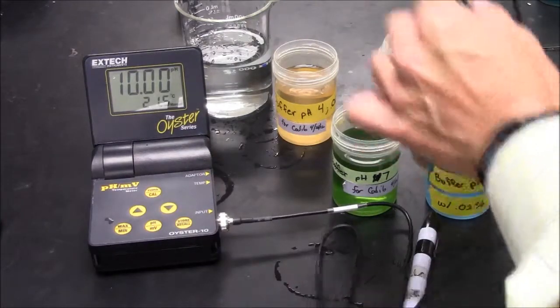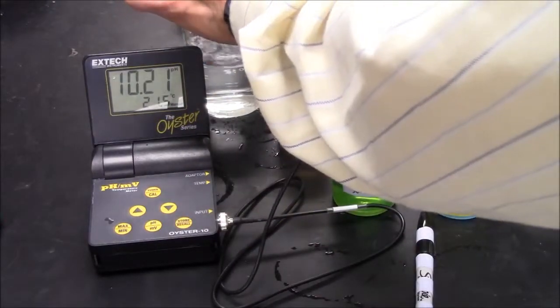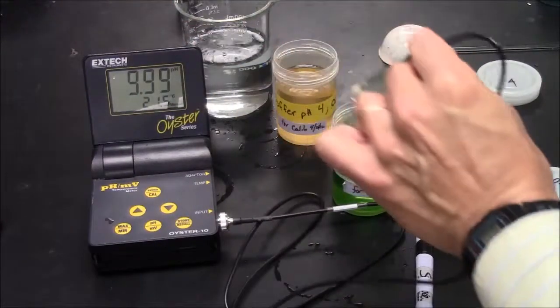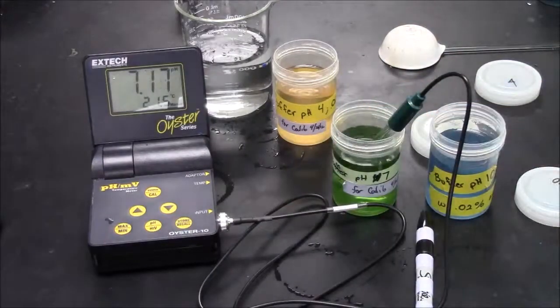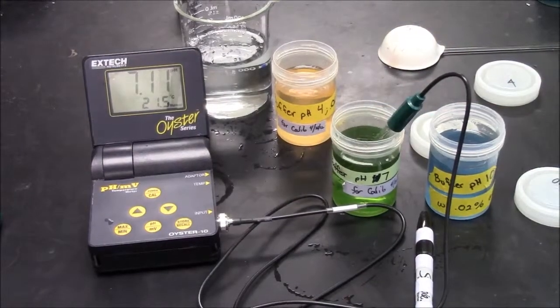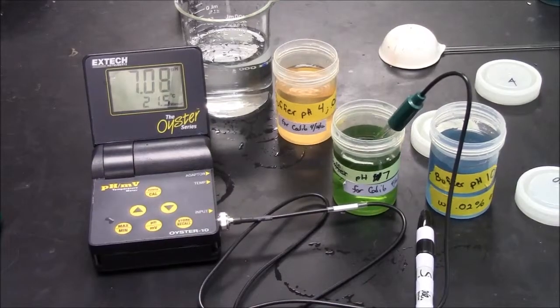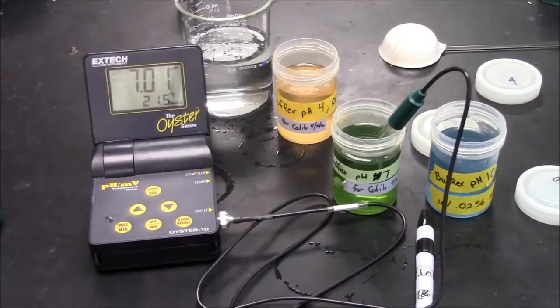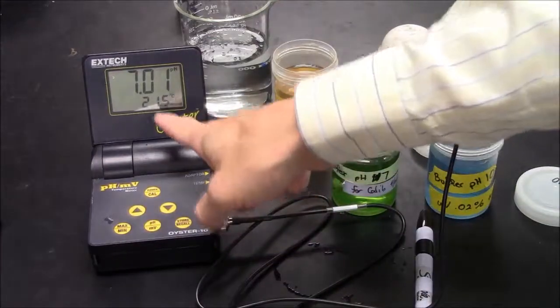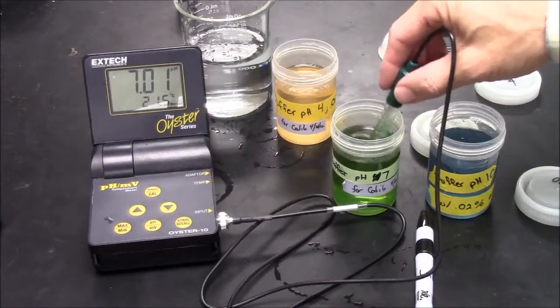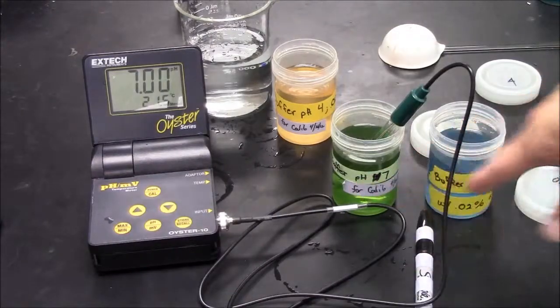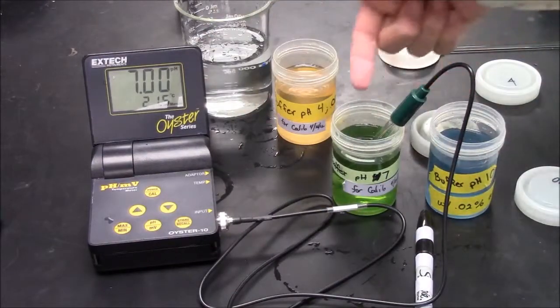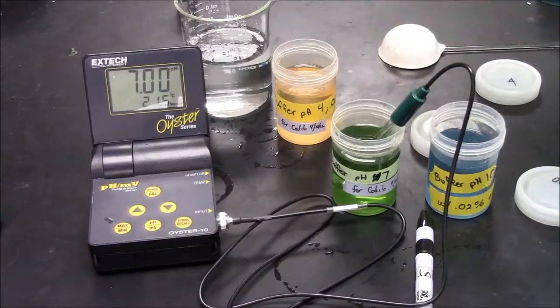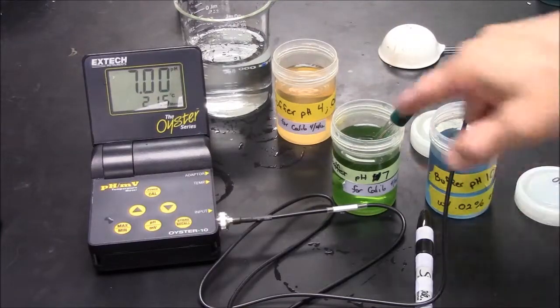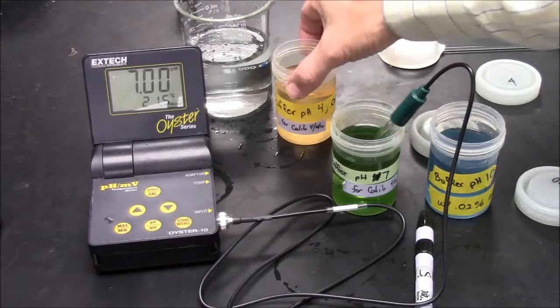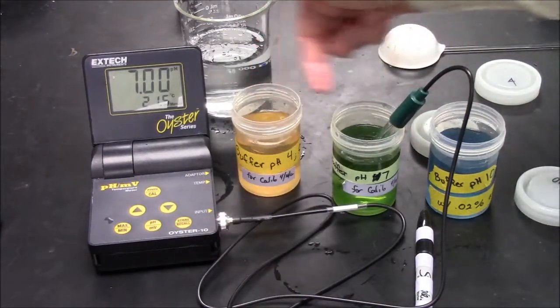I will now go back to pH 7 to make sure that that calibration point holds. Sometimes you have to go back and forth a few times before you can be convinced that it is calibrated correctly. I have to wait for a minute. Here you can see after a minute it's reading 7.01. I will say that's good enough. So this pH meter is calibrated between pHs 7 and 10. Probably could go a little higher than 10, a little bit lower than 7. But if I wanted to measure a pH of 5, I would recalibrate with 7 and 4.